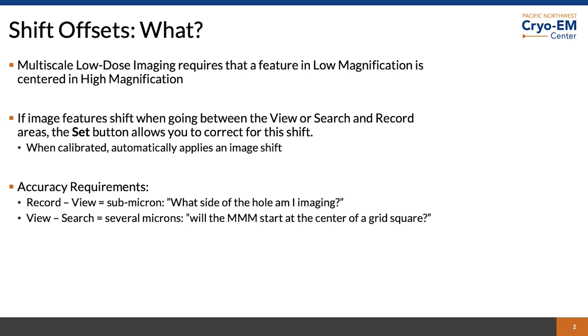For the record to view shift, you want to be on the right side of a hole. You want to image a small nanometer sized particle. If you're utilizing multiple exposures per hole, you want to target individual sides of a hole. So you need submicron accuracy. I would find a piece of contamination that is smaller than a hole, but large enough to see at both magnifications and then I would center it.